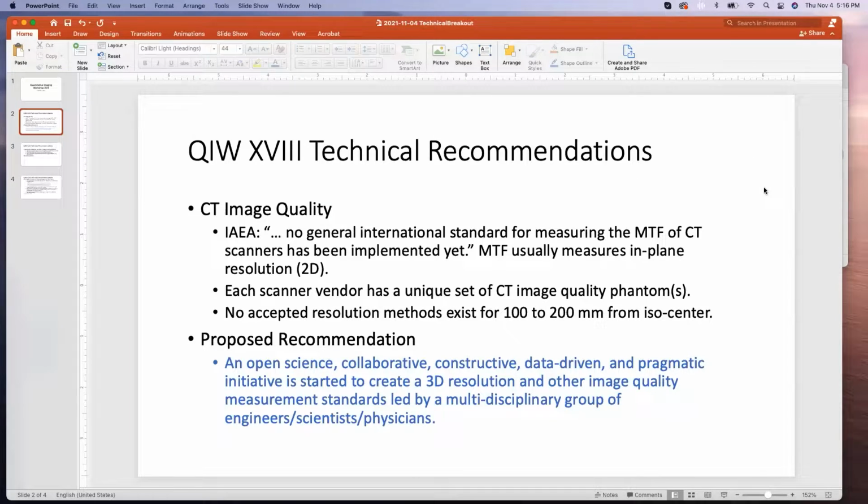Right now we have an idea from the physics of how precise the CT scanner should be able to be to meet that goal, but we have absolutely no calibration, and a suspicion that without any calibration evidence whatsoever from the manufacturer, we're not getting what the machine is capable of for these types of applications.